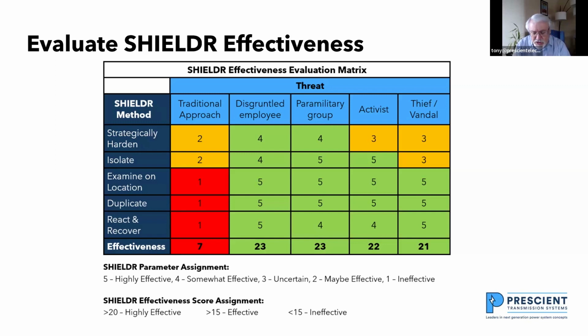If I want to strategically harden a substation, I could just convert that 3-pole switch to 3 single-phase switches. So then a disgruntled employee who wants to operate that switch to create a fault could open 1 phase, which would create a single-phase to ground fault, and that line would be tripped out of service, and he wouldn't be able to create a 3-phase fault.